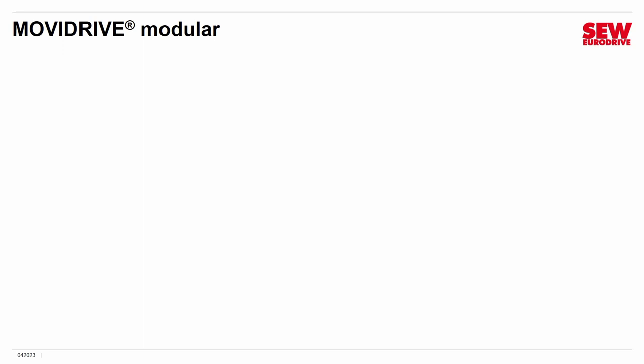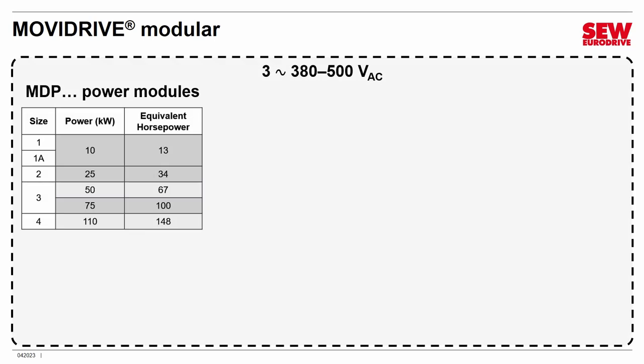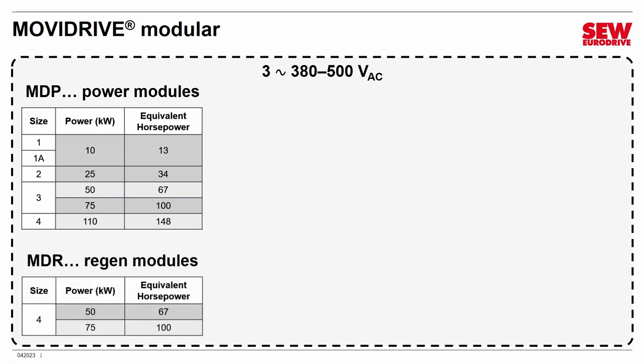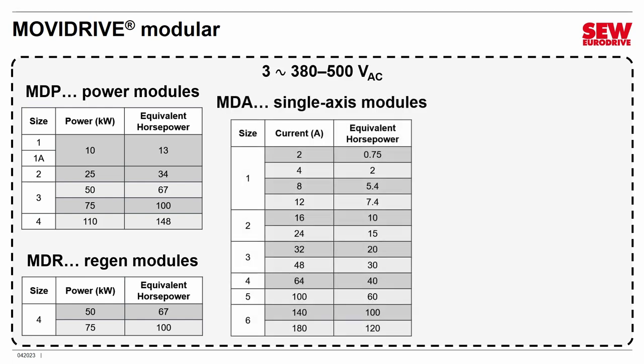MoviDrive Modular is somewhat different because you have the axis modules and the power supplies, so they each have their own sets of ratings. The power supply modules are all three-phase at 380 to 500 volts, coming in sizes from essentially 10 kilowatts to 110 — I've supplied the approximate equivalent horsepower as well. The single-axis modules range from size 1 to 6, handling from 2 amperes to 180, with equivalent horsepower from about three-quarters up to 120, so you can control motors from fairly small to pretty good-sized ones.